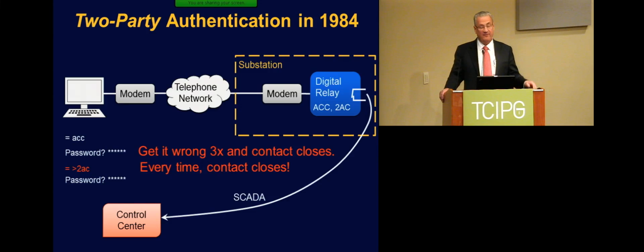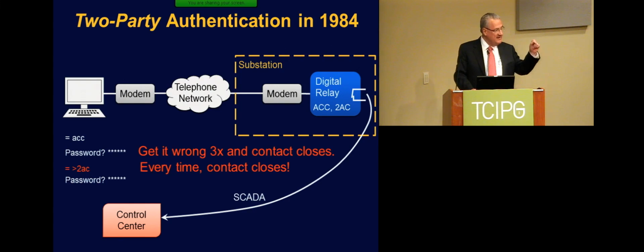So at that first access level, the only thing you can do is look at history and metering data. You cannot operate the breaker, you cannot set the relay. You cannot put software into it. That was it. So every time you put the second access command in, which depended on successful completion to that first access level, every time you even tried to get there, you'd bang the alarm contact again. Because now I thought you were doing something serious enough that the operator needs to know. We had customers tell us, would you disable that because we're irritating the operator? And we said, no, we will not. And we have not and won't.